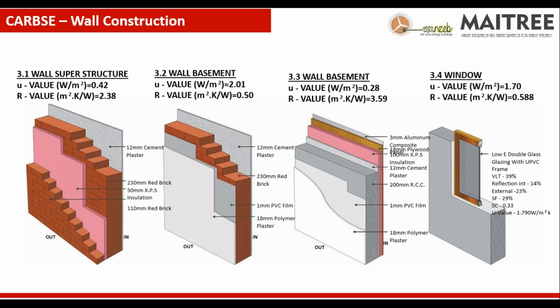But at the same time, whenever we operate in naturally ventilated mode, we should have enough thermal mass which gets charged over a period of time and can help us retain a lower mean radiant temperature for an extended period. That's why you see a 230 mm brick wall inside. Structurally, it wasn't required, but just to increase thermal mass, we thought let's have that. And now, after 4 or 5 years of operation, we feel it was a very good decision which we took at that point in time.